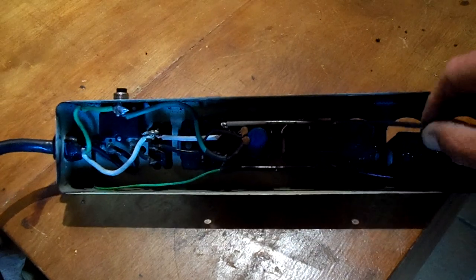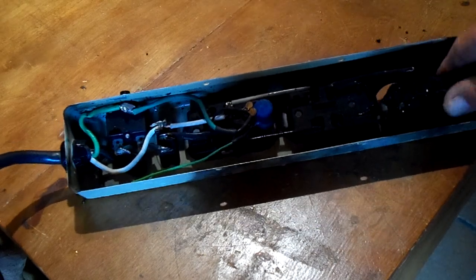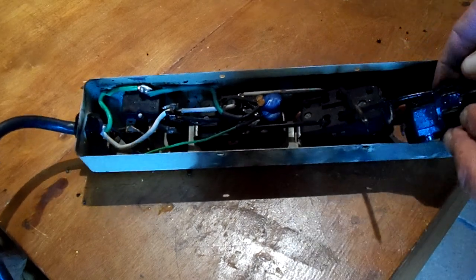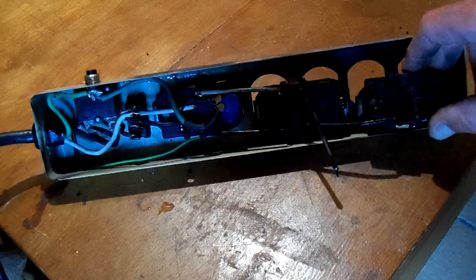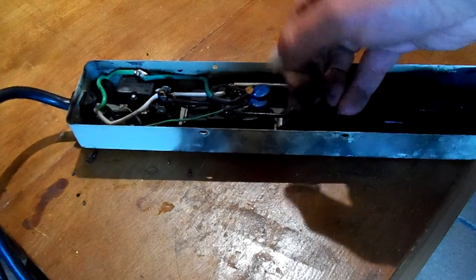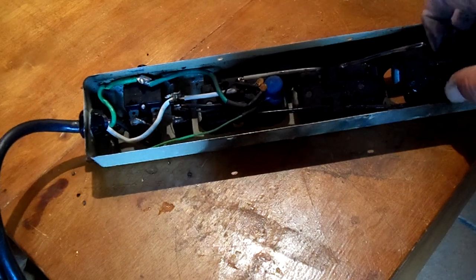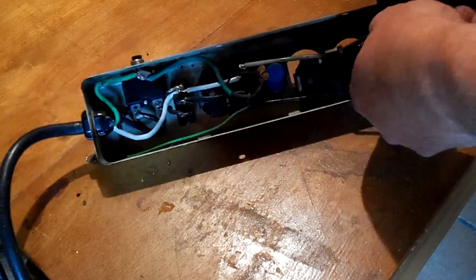Here's where the main damage is, where we saw the arcing. This is separated — this is one of the power transfer bars — and it has separated off of the plug and is not clamped anymore. It looks like it burned through where it was connected into the plug portion. Those are clipped in with these little clips right here, and that's where the most damage is. That piece is apparently melted off, and that's apparently where the electrical arc came from. I'm not sure what it would have grounded against to cause that arc though.